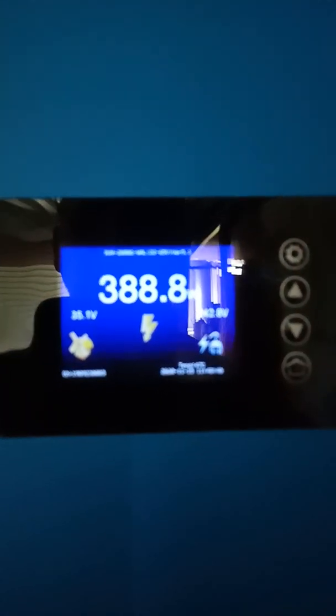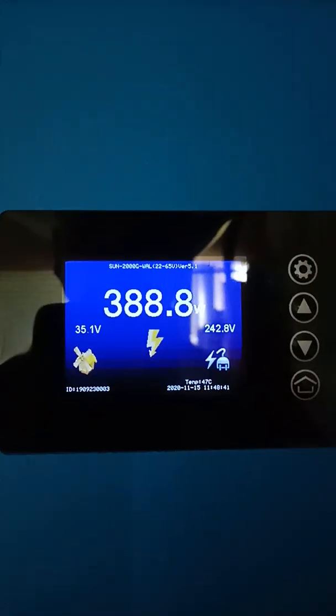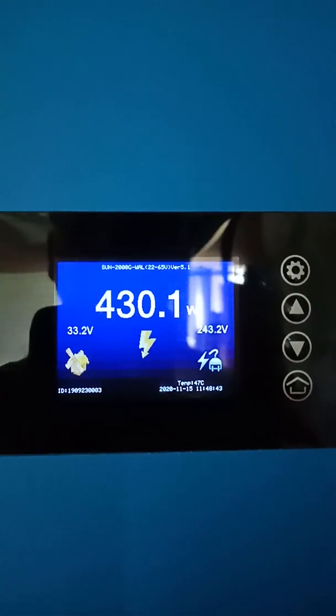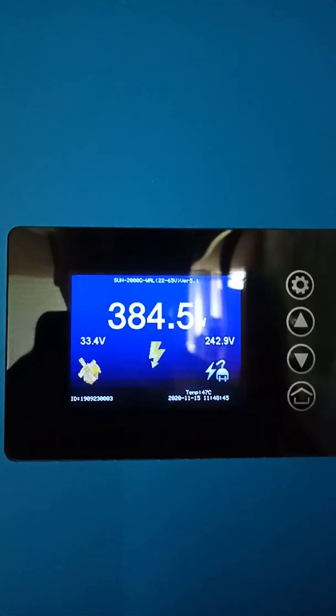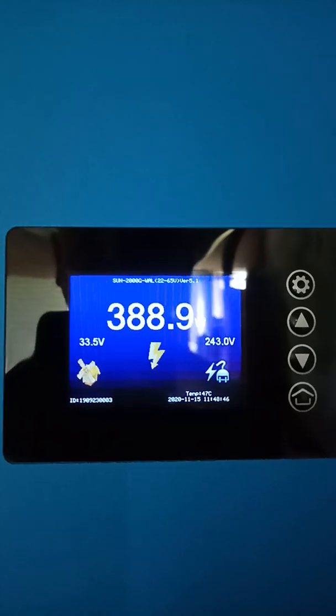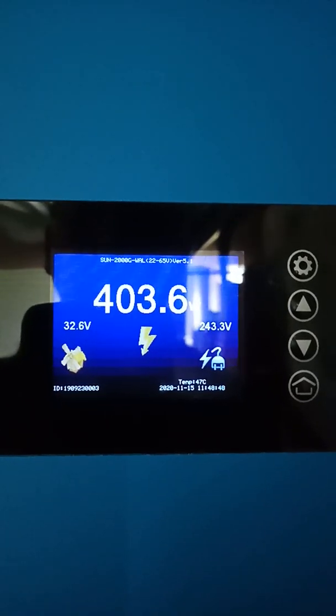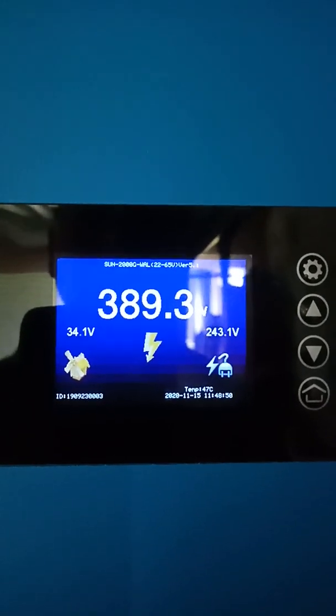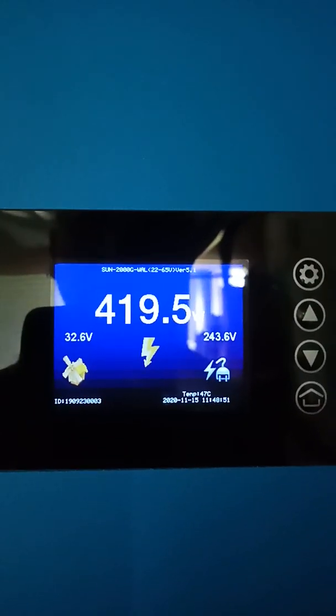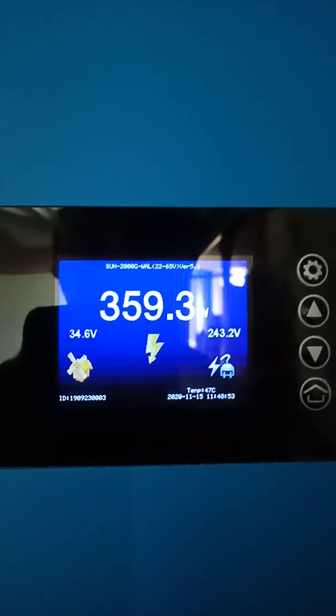So what you've got to watch for this is the mains voltage, which is 240 volts, which is okay. On a sunny day I can go right up to 250 because there's lots of solar on this subdivision where I am, and the more solar that they add, the higher the voltage goes and the grid just doesn't back off. It just keeps going up.